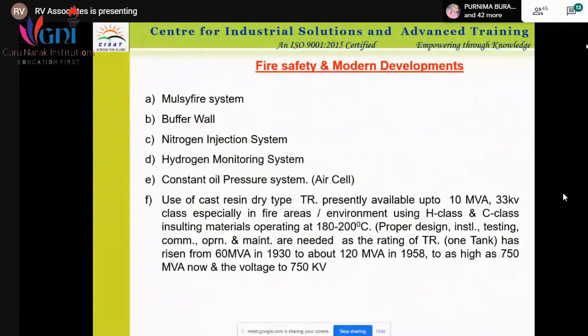Then there is another important system, which we call safety, so that all electrical equipment is safely monitored. We use fire safety, and for that all modern techniques are available. Emulsifier system is available. Then buffer wall we use. Nitrogen injection system is there. Hydrogen monitoring system is there. And one new advanced technology is also there: in case of fire in the transformer, it will cool or diminish the fire immediately, or as soon as possible.